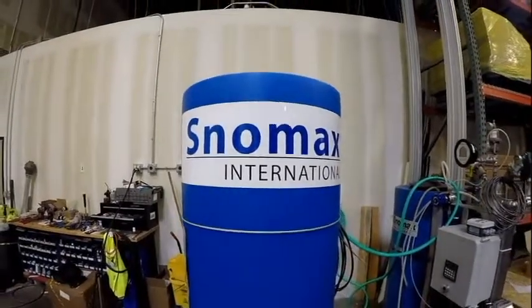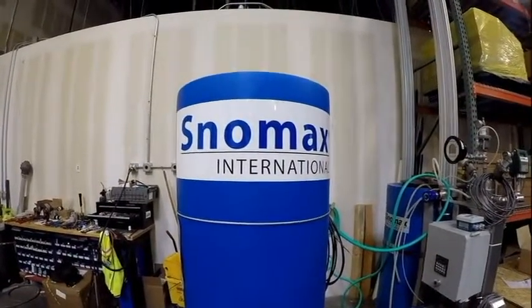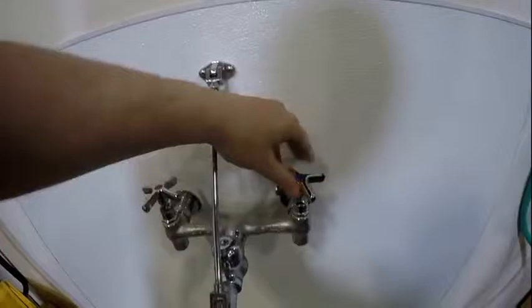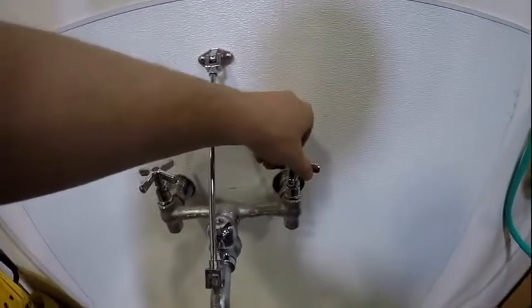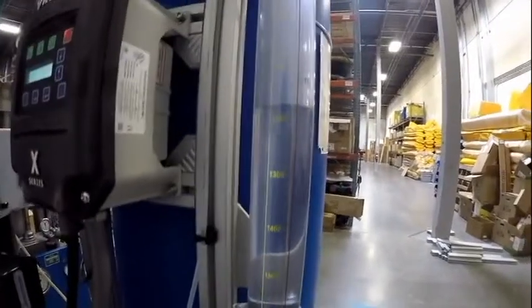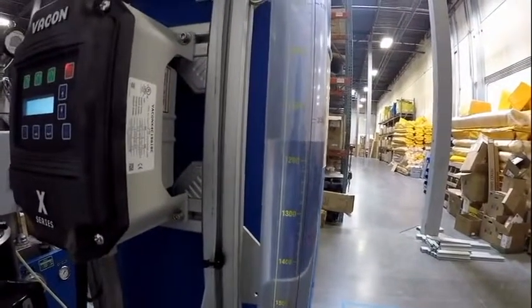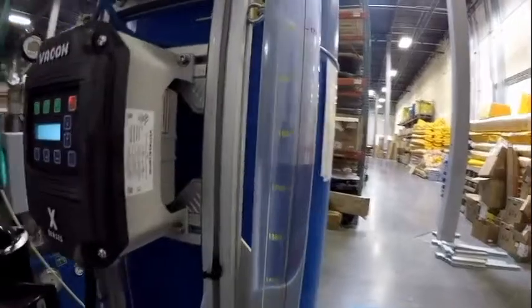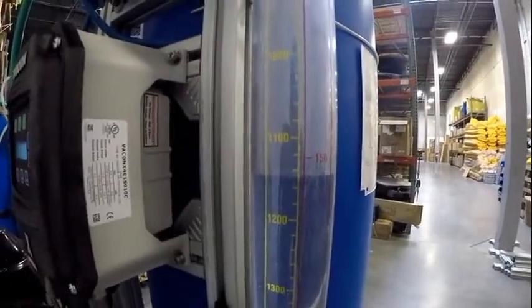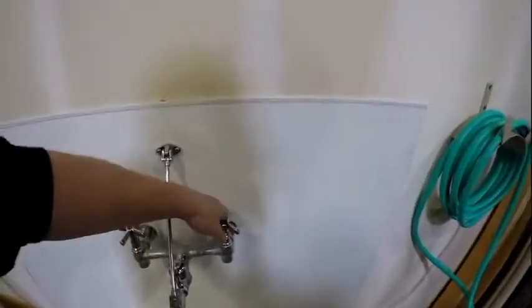Today we're going to be showing you how to calibrate your Snomax system. The first step is to fill the tank with water. We recommend about half of the tank to get the accurate calibration in the calibration tube. As you can see here, we're filling it up to about 150 liters. Turn that off.